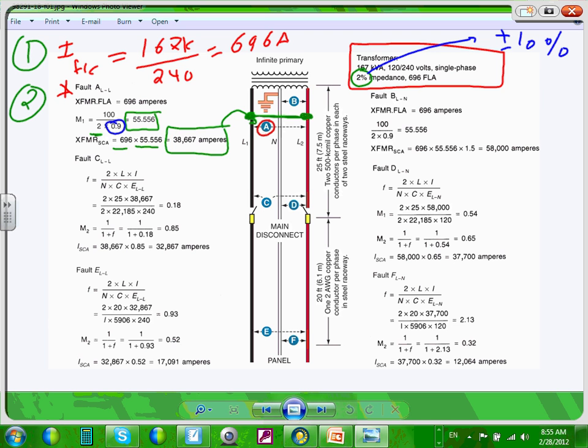So if it's plus or minus 10%, the worst scenario is minus. If I were to make this one 10% minus, how do you make a number 10% minus? You take 0.9 and multiply it. Here's the new impedance, and that's basically what they did here. Any question, guys, about finding the short circuit at the terminal of the transformer? Okay, now look what they're going to do.